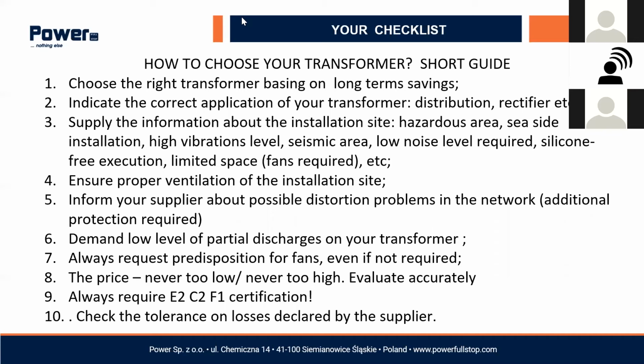Okay, it's also very important to inform your supplier if you know that there are some distortion problems in the network. This is just to be sure to get the right transformer and also the right protection inside the transformer. You're investing a lot of money by buying a transformer, 10, 12, 15,000 euro. Additional protection means maybe 0 cost or 10 euro, but it's protecting your transformer from any problem coming from the net. So if you have this information, just give it to your supplier.